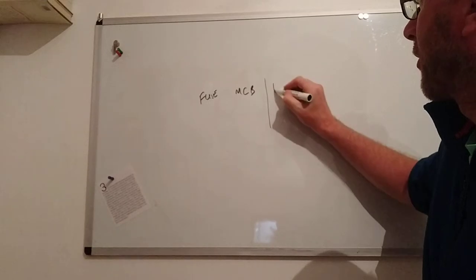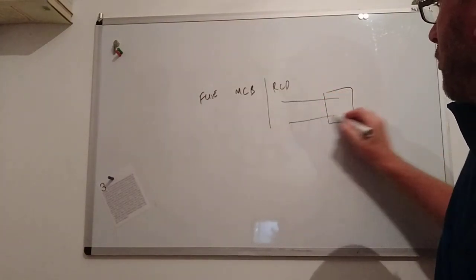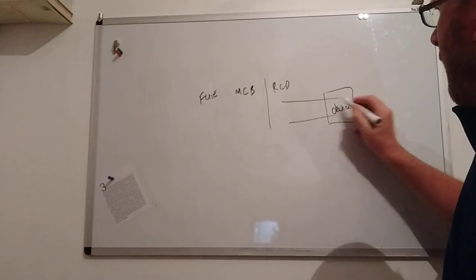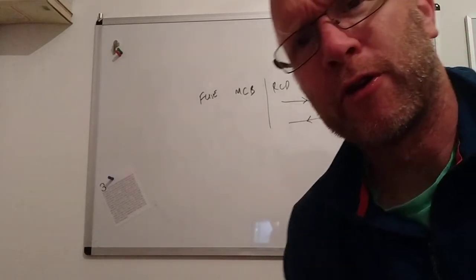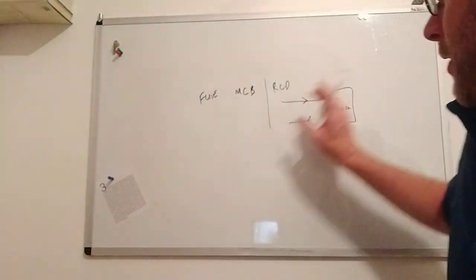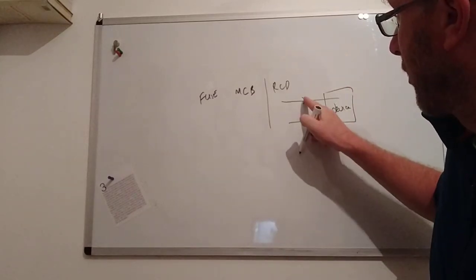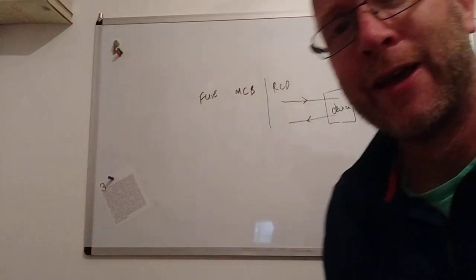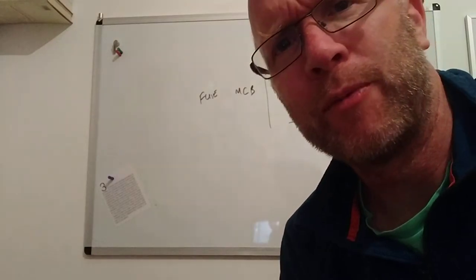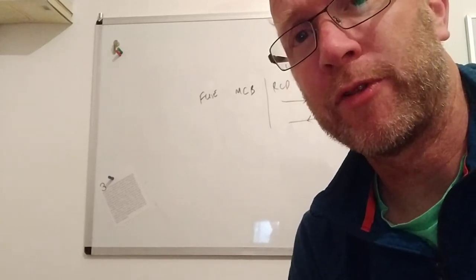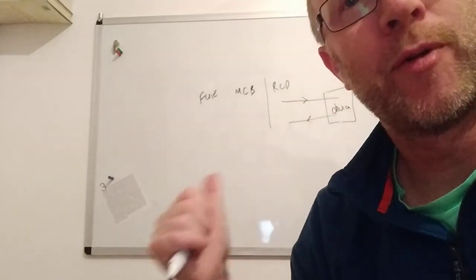The third type then is a residual current device (RCD), and this is different. The way an RCD works is we have a device with current in and current out. Now the current in should be equal to the current out. The current going in should be the current going out. If it's not, something funny has happened here and we could have a problem. So they measure the current going in and the current going out. If there's a difference of more than something like 30 milliamps, if there's a small difference, it turns off the circuit.